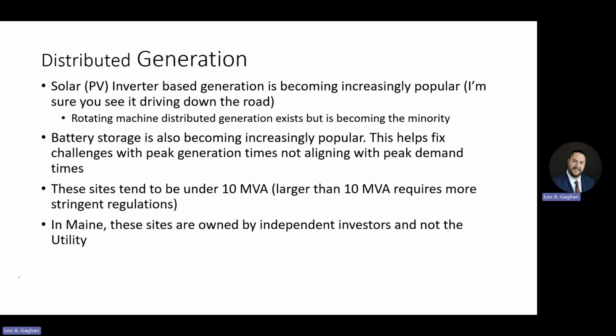Right? It's sunny during the day. Let's say in the wintertime it gets dark around 5. So solar is not going to do you much good at 6 when everybody gets home and turns the electric oven on all at the same time. So there's actually battery storage projects out there that just charge all day long at a certain rate, and then discharge when the demand is high at a higher rate. And that's how they make a profit. So it's becoming a popular thing. So these distributed generation sites are typically under 10 MVA. Larger than 10 MVA requires some more stringent regulations, modeling, things like that, studies. So they're usually under 10.